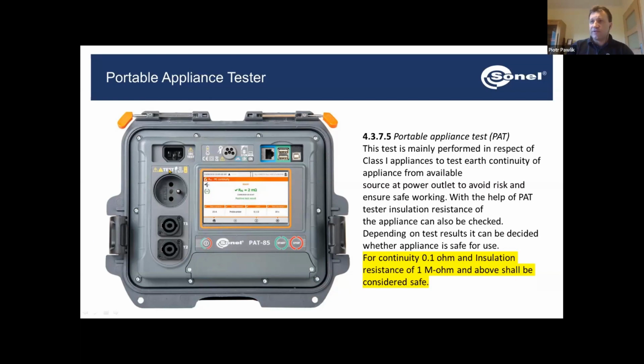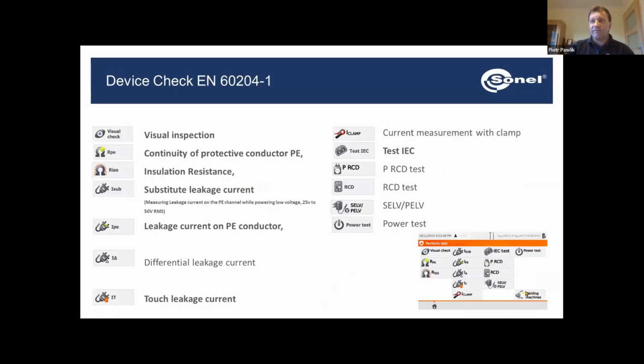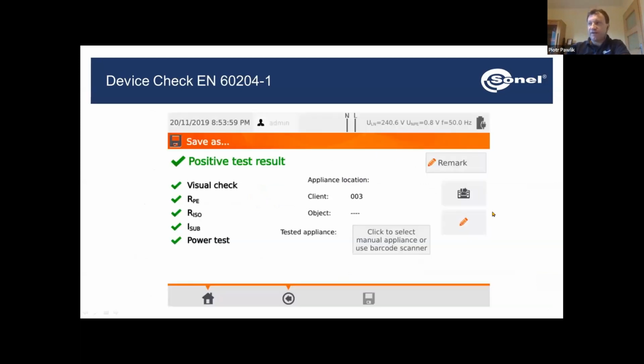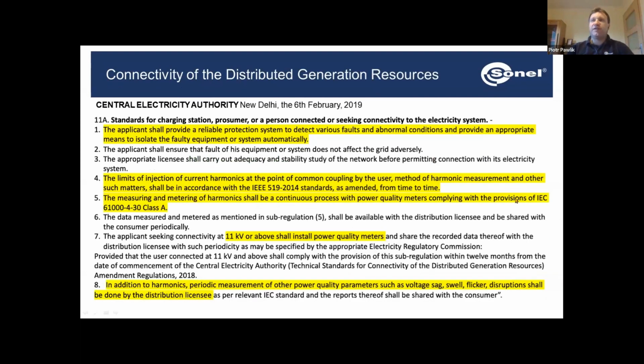Well, here on the screen you can see a European socket, but we have different sockets available for the meters. Besides that, with PAT meters, we can also check other parameters of portable appliances. Besides the continuity, we can check insulation resistance, leakage currents, power tests, IEC cable tests, so we can make sure that our electrical devices are safe. And that's the result on the screen.